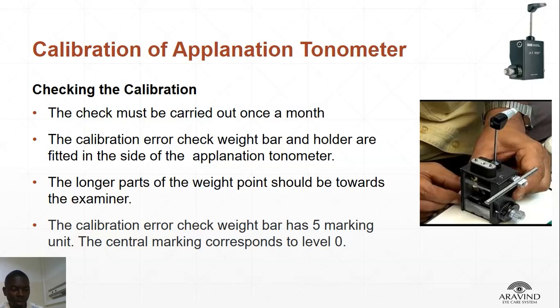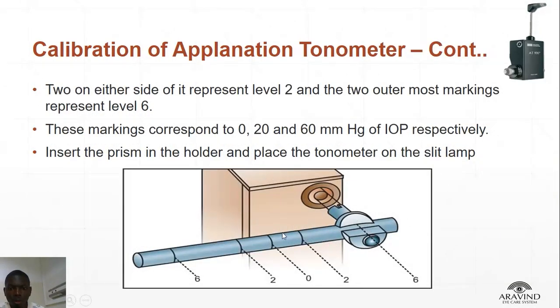We shall see in our next slide. Okay, you see, we have the center corresponding to 0. We have 2 on either side of it, and 6 on the outermost, so we make 5 points. The 2 on either side of the center represent level 2, and the 2 outermost markings represent level 6. You see 2, 2, 6, 6. These markings correspond to 0, 20, and 60 millimeters of mercury respectively. Insert the prism in the holder and place the tonometer on the slit lamp.